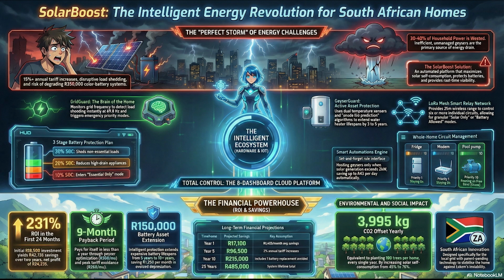That's terrifying for a R150,000 asset. And doing this once or twice might not show immediate catastrophic damage, but doing it consistently, imagine a prolonged stage 6 load shedding scenario. Okay, let's play that out. The grid is down for 4 hours. It's a cold evening. Your battery is constantly fighting to keep heavy appliances, heaters, ovens, geysers running without any grid support. It drains down to 2%.